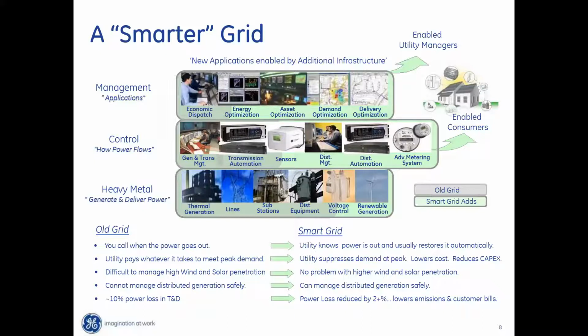Reactive power control. And we've done that separately for a long, long time to improve the power factor on the grid. The difference today, that's the light gray part. See, it's shaded halfway here on the bottom. The light green part of this is today we're integrating voltage control and reactive power control. We call it integrated volt-VAR control or volt-VAR optimization, okay? We're integrating many more distributed generation, renewable generation into the grid.